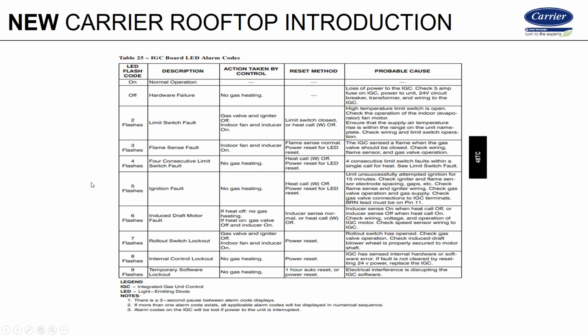So if we get multiple 3s, and as you see here on the 5, it's going to attempt for ignition for 15 minutes. If we don't get ignition, it will issue a 5 and lock out. Well, give it 3 hours and it's going to go back and retry again. Okay? So 3 is related to 5, like 2 is related to 4, okay?